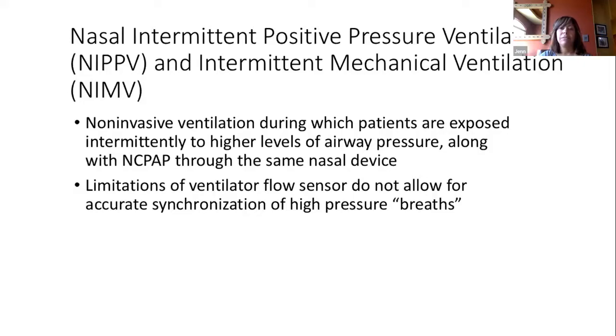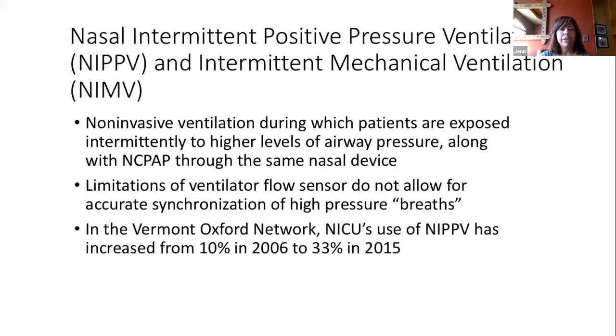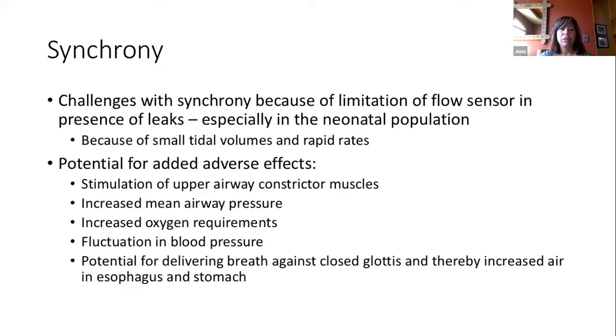There are limitations in terms of the vent flow sensors, and this is one concern when providing NIPV: we cannot provide it in a synchronous fashion, really, because of the limitations of the flow sensors on the ventilators. And so it's really hard to produce an accurate synchronization of the high pressure breath. And NIPV is increasing in use throughout the US and Europe. In terms of synchrony, the limitations, like I said, the flow sensor isn't good at catching the leak and being able to compensate for that, especially in the neonatal population, just because neonates have much smaller tidal volumes and a lot faster rates than the adult population.